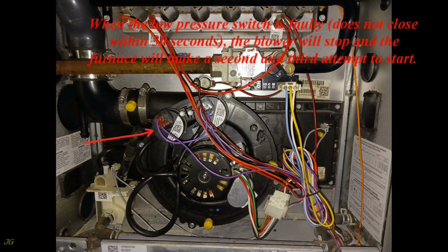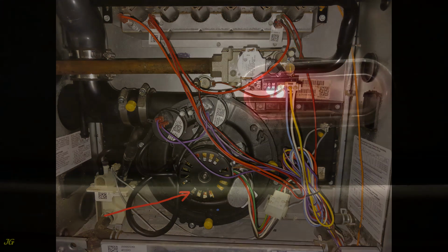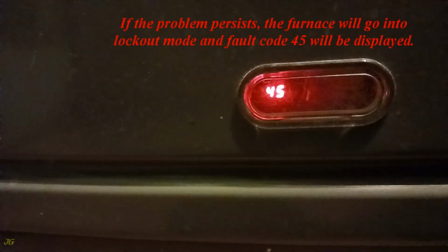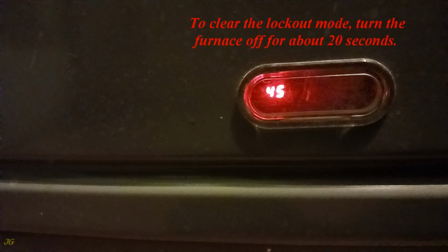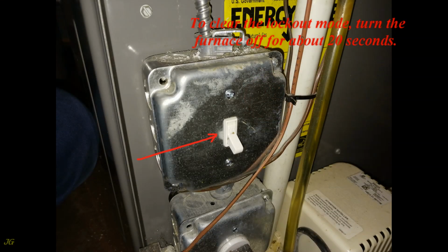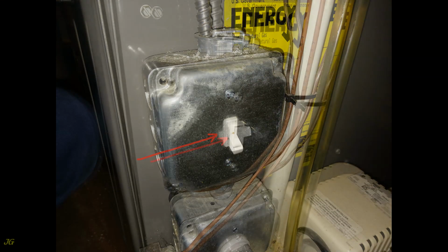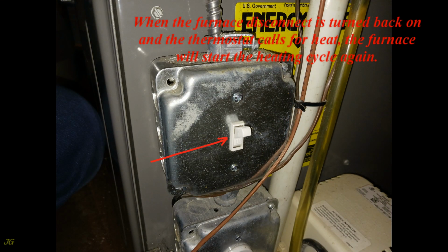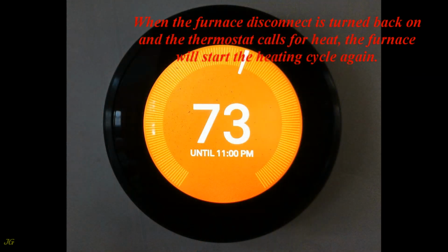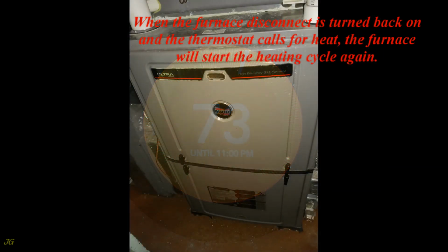When the low pressure switch is faulty and does not close within 30 seconds, the blower will stop and the furnace will make a second and third attempt to start. If the problem persists, the furnace will go into lockout mode and fault code 45 will be displayed. To clear the lockout mode, turn the furnace off for about 20 seconds. When the furnace disconnect is turned back on and the thermostat calls for heat, the furnace will start the heating cycle again.